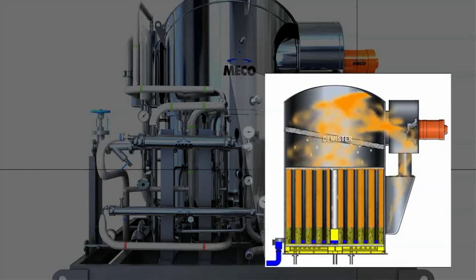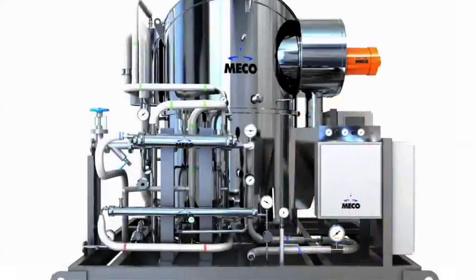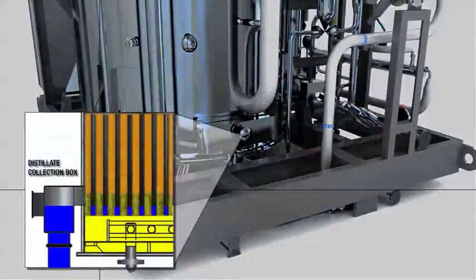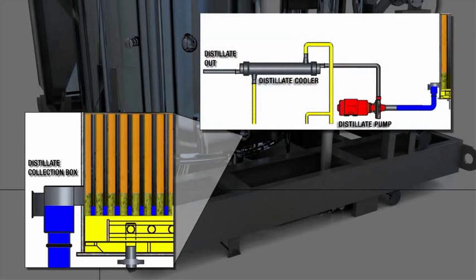Entrained water droplets which have been removed by the demister return to the process. Vapor condenses on the outside of the evaporator tubes forming distillate. Distillate drips down the tubes, is gathered in the distillate collection box, and is then pumped out by the distillate pump through a cooler and out of the still for use.